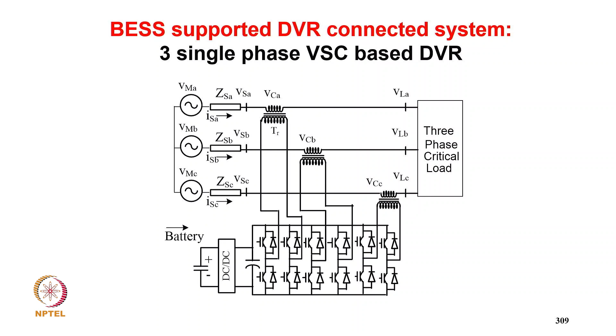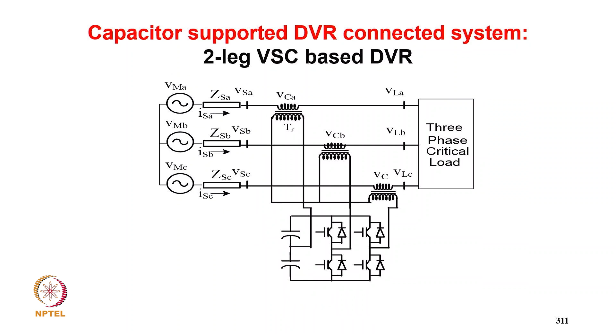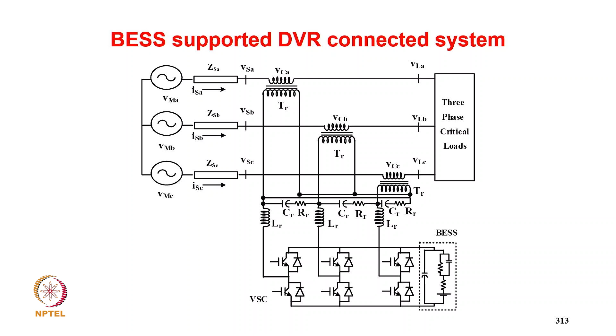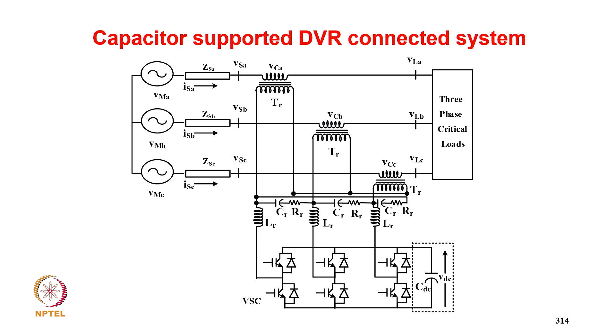So we have a capacitor, but there is a limitation that you cannot feed power to change the angle. Because it does not have much energy or power on the DC link, you have to inject either harmonic voltage or voltage at the quadrature axis, so that you don't need real power to support the midpoint. This is 3 single phase capacitor support. And this is battery supported on the DC link with a 3 leg voltage source converter.